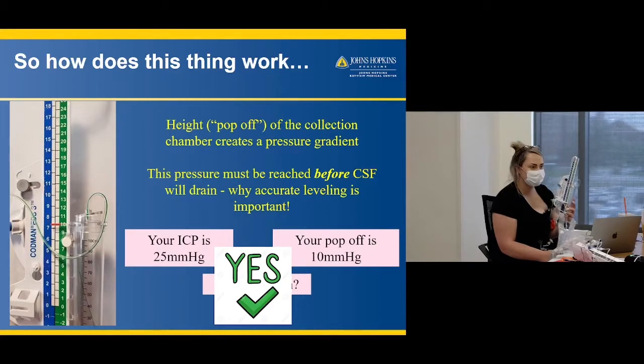Sure. So a lot of it depends on the reason why you're putting this in and how much you want to drain. If it's a trauma patient and they've got severe cerebral edema, it's always going to be 0. They're just going to put it at 0 and let it drain all the time. If it's a subarachnoid patient or it's an intraventricular bleed and you don't want to over drain and get too much stuff out of there, then they might set it at 10 or 15. So it drains a little bit. It gives them some safety to get some of that off if their ICPs rise, but it's not going to constantly drain. But if your ICP is higher than the pop-off, then it's always going to be draining.